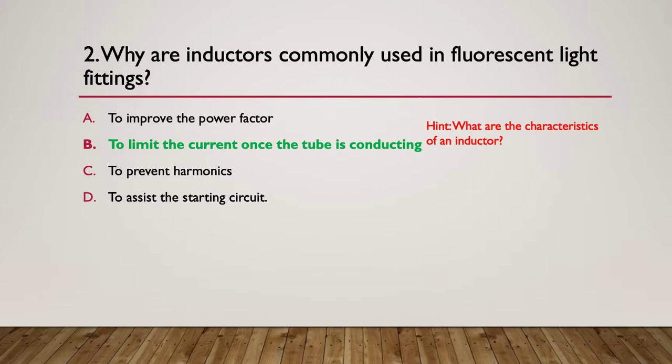It's used to limit the current once the tube is conducting. That's what it's very good at. Until the tube strikes, no current, therefore no restriction of current through the inductor. But once the tube conducts, the impedance of the gas in the tube goes from several megaohms down to a fraction of an ohm. Therefore, the inductor then limits the current.